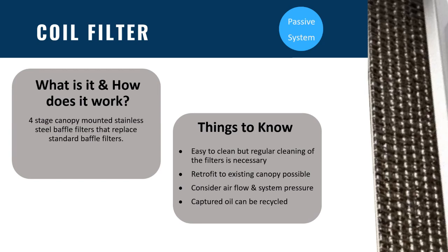So, things to know about this system. They're easy to clean, but regular cleaning of the filters is necessary. You do have to give consideration to airflow rates and the system pressure. Retrofitting to existing canopies is possible. And a nice feature about this is that the captured oil can be recycled. There are no chemicals involved in this process, and the capital investment required is low to medium, depending on how many canopies and how many filters are in the kitchen.